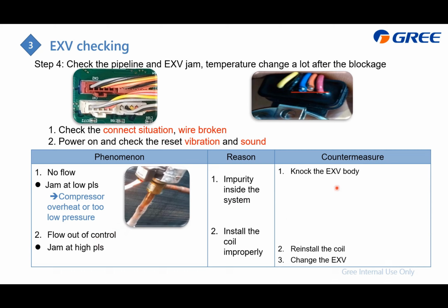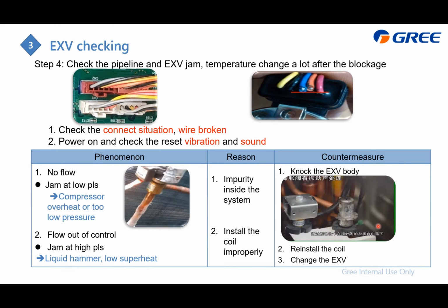And our countermeasure for this one is just the other one. For this, maybe this time the inside pin is stuck or jammed at the high pulse. At that time, too much refrigerant flows back to the compressor, which will also lead to liquid hammer. And our countermeasure for it is to use your screwdriver to knock this EXV body, and for maybe 70% you can make these impurities go through. And the next is just to install the coil or just replace the EXV.